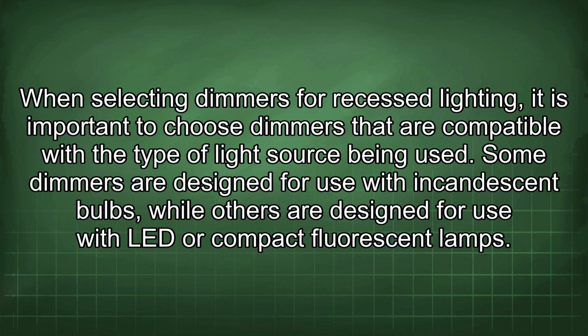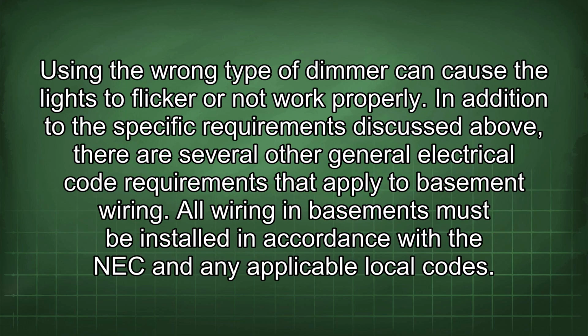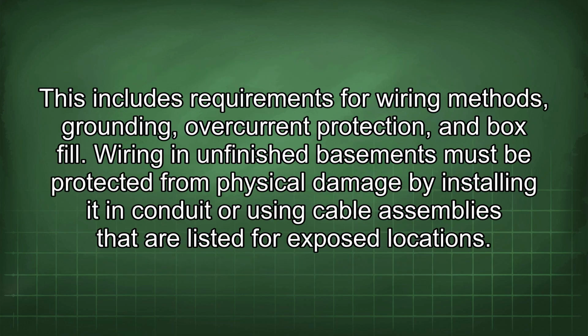Some dimmers are designed for use with incandescent bulbs, while others are designed for use with LED or compact fluorescent lamps. Using the wrong type of dimmer can cause the lights to flicker or not work properly. In addition to the specific requirements discussed above, there are several other general electrical code requirements that apply to basement wiring. All wiring in basements must be installed in accordance with the NEC and any applicable local codes. This includes requirements for wiring methods, grounding, overcurrent protection, and box fill.